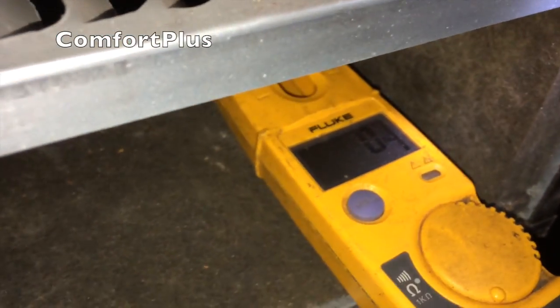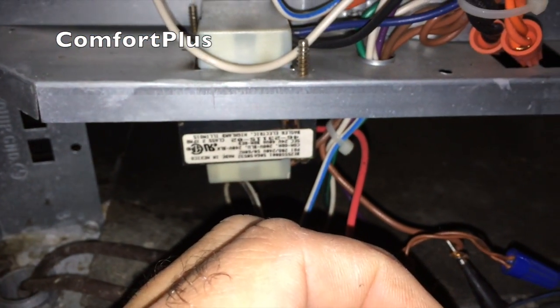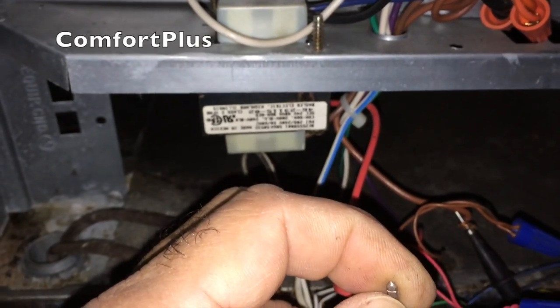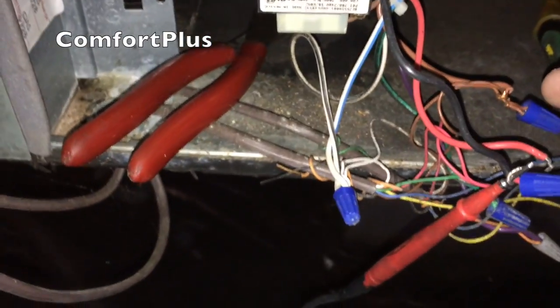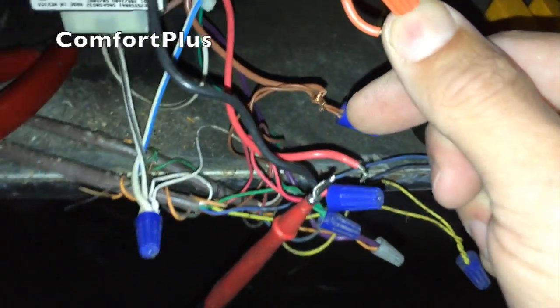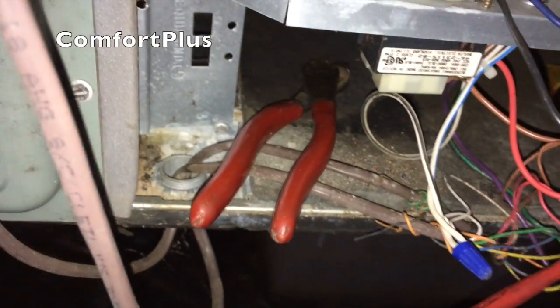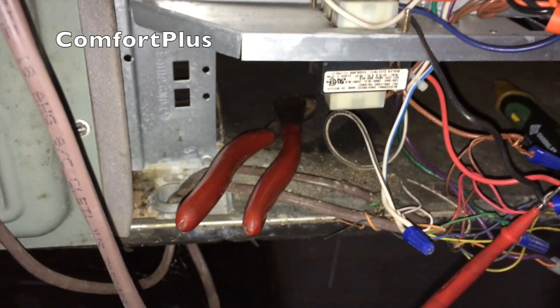Okay guys, we have 0 volts coming out of the transformer. So I'm going to unwire the transformer and check continuity. Okay folks, the secondary side of the transformer has 2 ohms. It does have continuity, you can tell by the beeper. Okay, and we'll check the primary side, and it is open. So the primary side of this transformer is open.